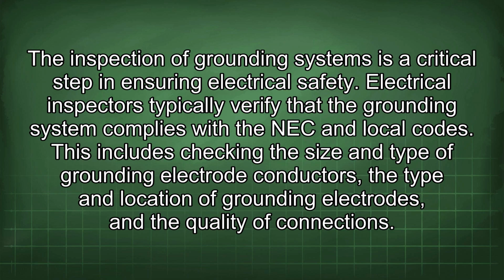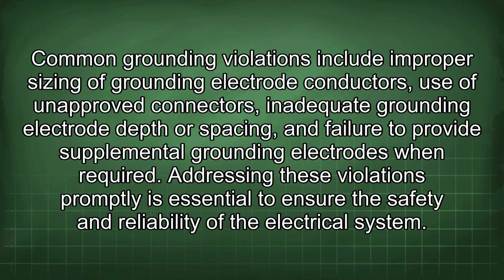This includes checking the size and type of grounding electrode conductors, the type and location of grounding electrodes, and the quality of connections. Common grounding violations include improper sizing of grounding electrode conductors, use of unapproved connectors, inadequate grounding electrode depth or spacing, and failure to provide supplemental grounding electrodes when required. Addressing these violations promptly is essential to ensure the safety and reliability of the electrical system.